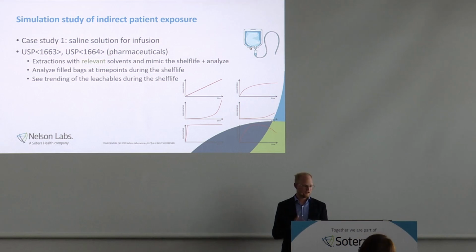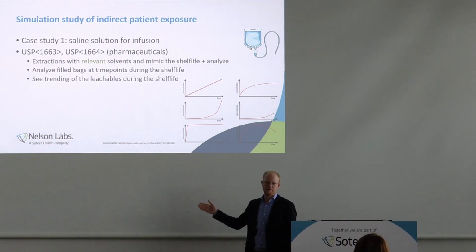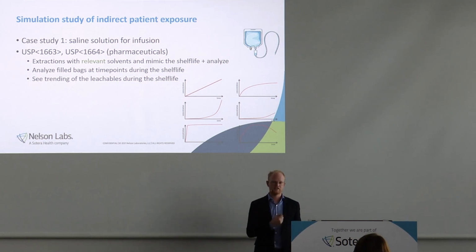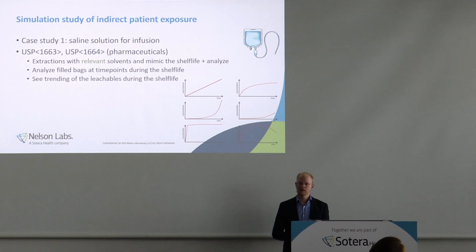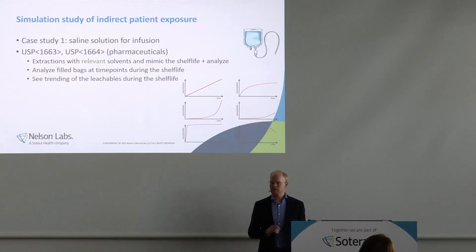And important is also that you test your leachables in this case. We can talk about leachables because we are simulating the use. We can do multiple time points within a shelf life. For instance, you have freshly produced bags, time point 0, after 3 months, 6 months, 12 months, 18 months. We take a sample, we analyze the saline solution, and we can analyze for leachables. Saline solution is a very good solution because also from an analytical point of view, that's a clean solution. It doesn't interfere, it doesn't introduce any noise in our analysis. So this is very, very meaningful.